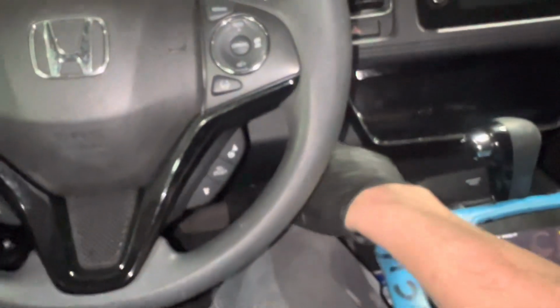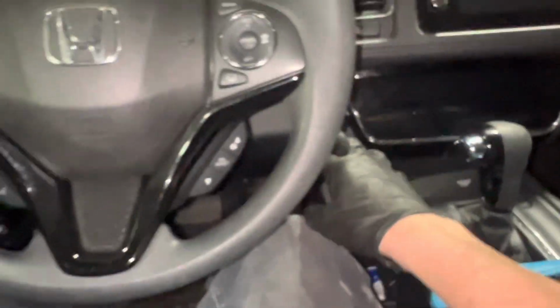Oh, and high pressure nitrogen leak testing — using nitrogen is another method. Another method for leak testing is helium or hydrogen, with a leak detector meant specifically for helium and hydrogen. In Europe, they actually have stricter laws about using refrigerant itself as a leak test item.